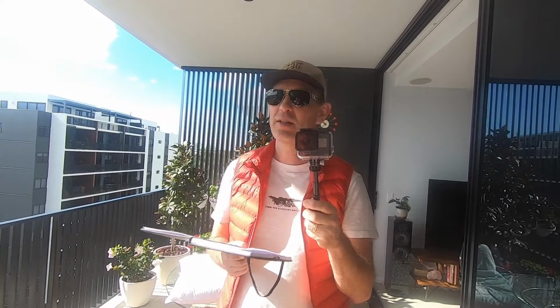That takes about a minute. You do need to swap the settings around to make sure everything's well. So once that whole full test, which is 2 components, is done, it should be followed with a low pressure test. That's done through the common gas outlet with a little bulb. Did you like the sound effects? A little bulb, and you squeeze all the air out of the common gas outlet line, and then you wait for that bulb to stay flat and deflated for 30 seconds. And of course it just becomes a sound effect again, big bulb. Yeah, and then if there's a leak you have to fix it.